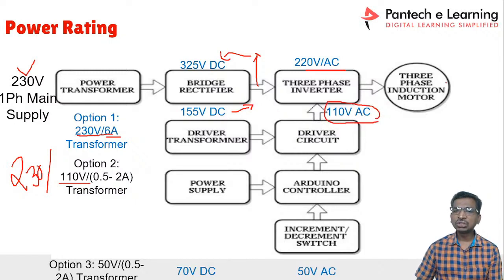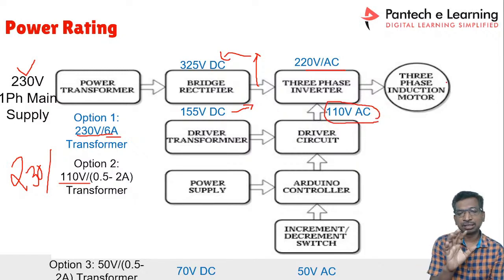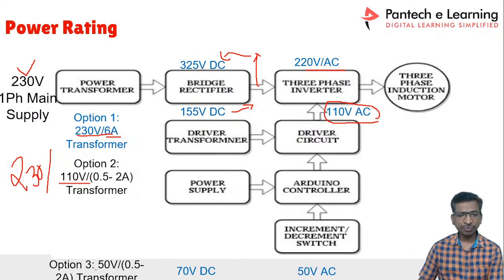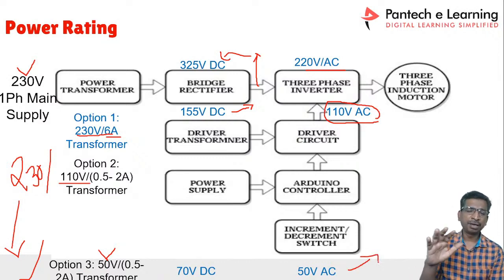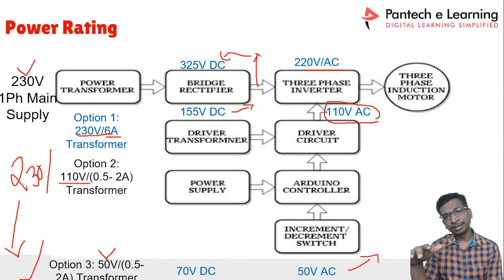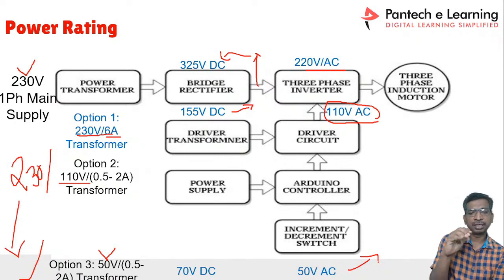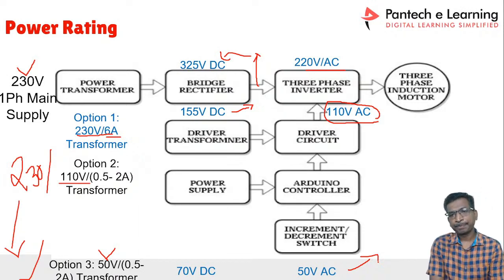For this range also, the speed control logic will work. Option 3 also you can use, still with 230 primary and 50 voltage secondary. The output voltage will be 50 hertz, 50 voltage AC. But the speed will not be the rated speed, it will be somewhat less, because you are applying only around 50% to 70% of the voltage. So in that case, you can use this reduced step level.